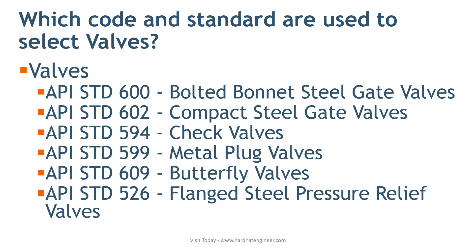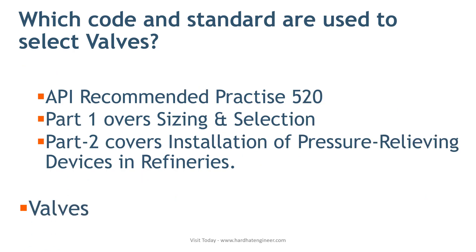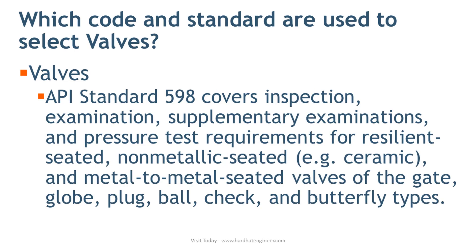API standard 526 covers flanged steel pressure relief valves. API Recommended Practice 520 Part 1 covers sizing and selection, and Part 2 covers installation of pressure relieving devices in refineries. API standard 598 covers inspection, supplementary examination, and pressure test requirements for both resilient seated and metal-to-metal seated gate, globe, plug, ball, check, and butterfly valves at the valve manufacturer's plant.